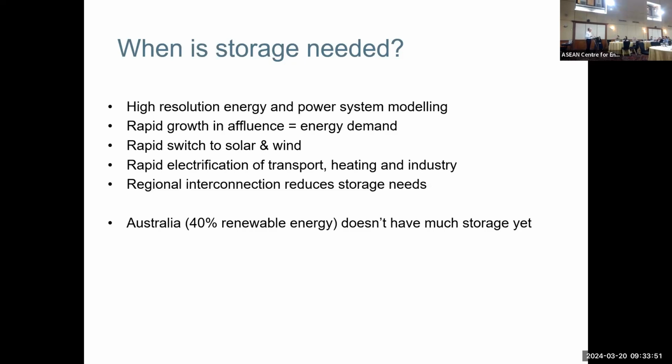And regional electrification, regional interconnection reduces the need for storage. So we looked at this quite closely for Australia. If each state in Australia went it alone and developed 100% renewable energy just within itself, you need 5 times more storage than if we interconnected the states.